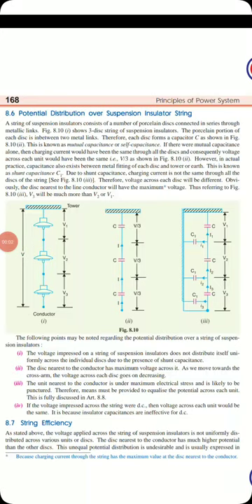Hello dear students, welcome to the Transmission and Distribution class. In the previous class we saw the different types of insulators. Today we will see how potential distributes over a suspension insulator string. Suspension insulators are used in a string — meaning a number of disks are used together depending upon the voltage level. If we have a 33 kV system, we use a string of three disks cascaded together.